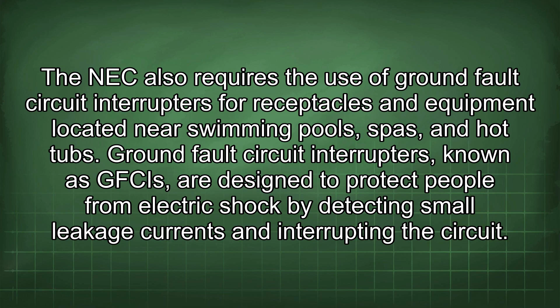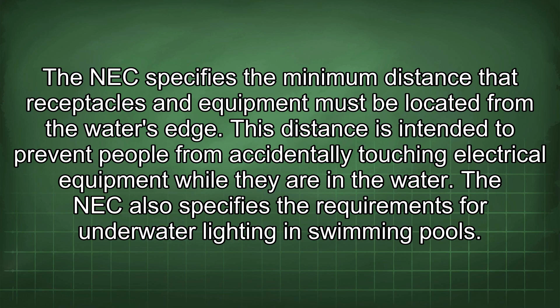The NEC specifies the minimum distance that receptacles and equipment must be located from the water's edge, intended to prevent people from accidentally touching electrical equipment while in the water. It also specifies requirements for underwater lighting in swimming pools, which must be listed for such use and installed according to the manufacturer's instructions.